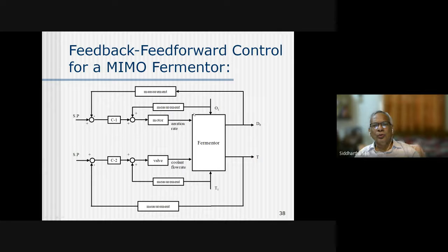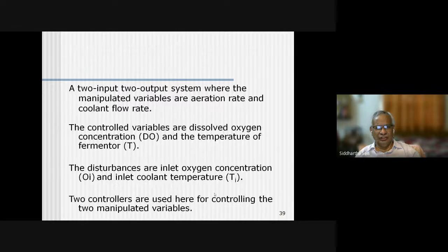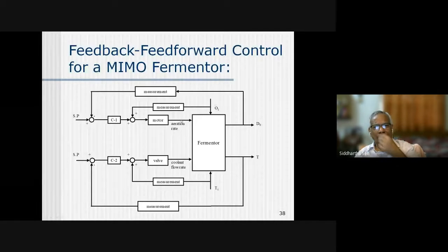So there are two disturbances, OI and TI, which need to be measured and fed forward: the inlet oxygen concentration and the inlet coolant temperature. We are giving this aeration based on the inlet oxygen concentration and the coolant temperature, because these two need to be measured, giving us a feedback plus feed forward scheme that produces a good quality product.